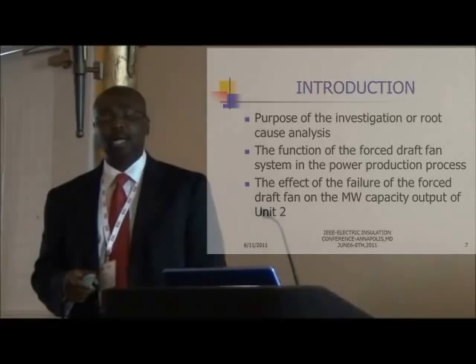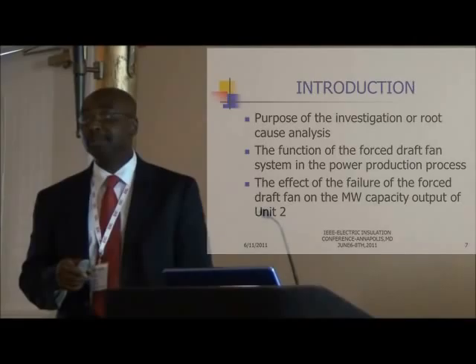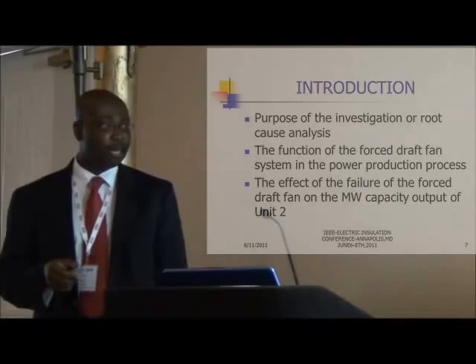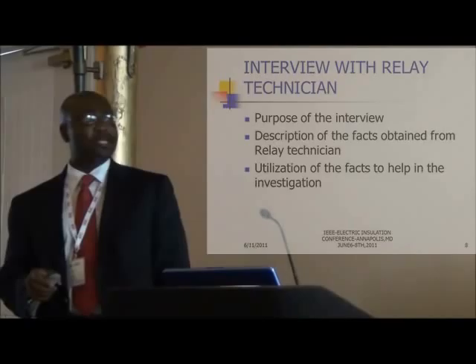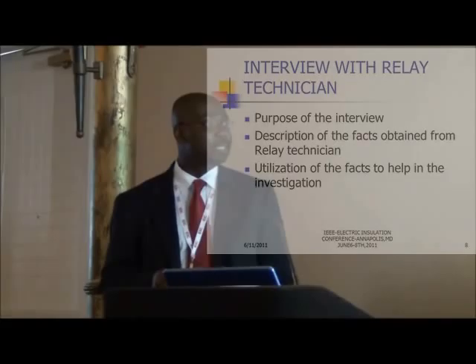The purpose of the investigation was to find out what actually caused the motor to fail. A forced draft fan in a coal-fired power plant helps with the combustion process of the boiler. The failure of the force draft fan can lead to a reduction in the megawatt capacity output of Unit 2 and a loss of revenue. When the motor failed, the first thing we did was conduct interviews with the relay technician on duty to gather facts and guide the root cause investigation.